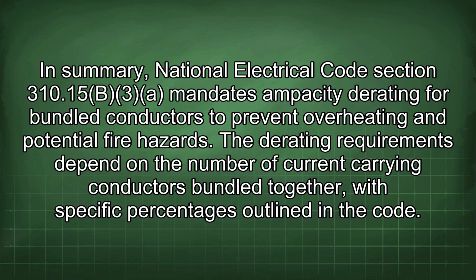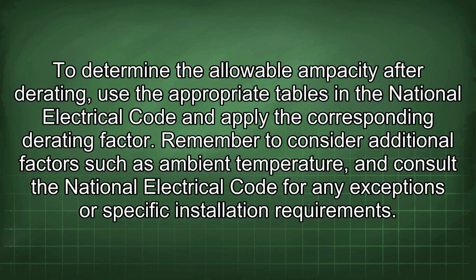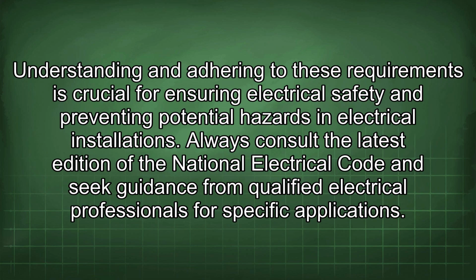The derating requirements depend on the number of current carrying conductors bundled together, with specific percentages outlined in the code. To determine the allowable ampacity after derating, use the appropriate tables in the National Electrical Code and apply the corresponding derating factor. Remember to consider additional factors such as ambient temperature, and consult the National Electrical Code for any exceptions or specific installation requirements. Understanding and adhering to these requirements is crucial for ensuring electrical safety and preventing potential hazards in electrical installations. Always consult the latest edition of the National Electrical Code and seek guidance from qualified electrical professionals for specific applications.